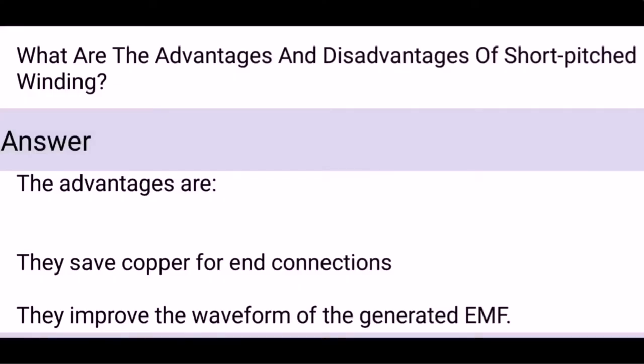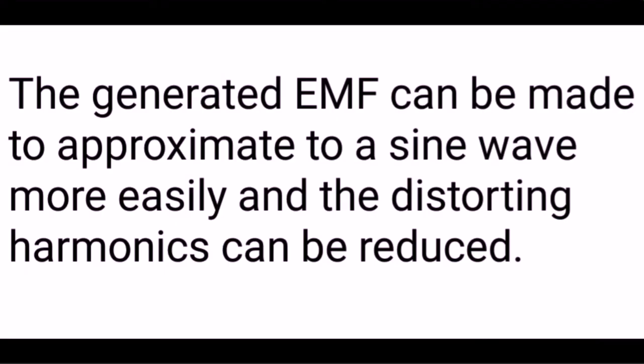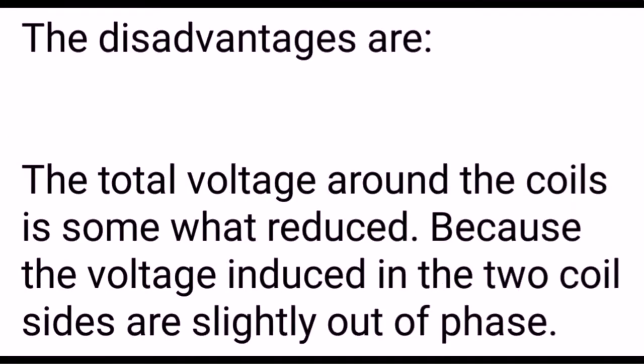What are the advantages and disadvantages of short-pitched winding? The advantages are: they save copper for end connections, they improve the waveform of the generated EMF, and the generated EMF can be made to approximate a sine wave more easily while distorting harmonics can be reduced. The disadvantage is that the total voltage around the coils is somewhat reduced, because the voltages induced in the two coil sides are slightly out of phase.